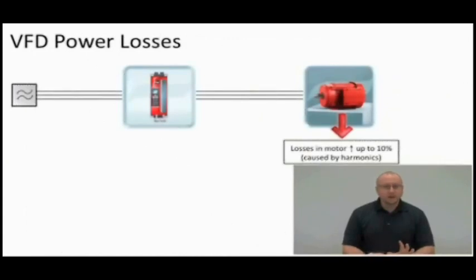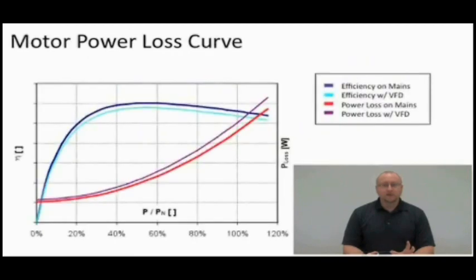So let's just review the VFD power losses real quick. The first thing is you can have harmonic losses in the motor, actually up to 10%. If we look at these curves, you can see the difference between the efficiency of a motor if you run it just on the mains, and on the mains I mean just putting AC power directly into it with no inverter, versus using an inverter or a variable frequency drive. The light blue line you can see is just a little bit lower, so it is a little less efficient if you use a frequency inverter, and this is what I'm talking about, the motor coupled with a frequency inverter.